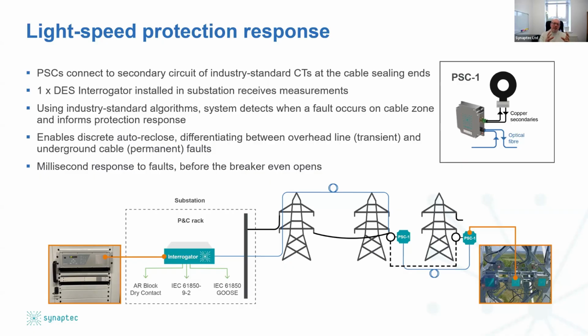So all of our interrogators are ready to deploy now on conventional schemes. But if you're ready to go to 61850 or you're thinking of going digital soon, the interrogator's already ready to do that. 61850 is built in. Okay, so it's future proof. And fundamentally, it means you'll have millisecond timescale and very reliable and robust response to faults, no matter how far away they are. In the case that I just mentioned to you, where one of our sensors is 60 kilometers away from the interrogator, you'll still see that fault and we'll still be able to receive that information, process it, timestamp it, and publish it all within milliseconds before the breaker even operates. The system will know if it's safe to reclose. We're talking 9 to 10 milliseconds as a typical operation time here.